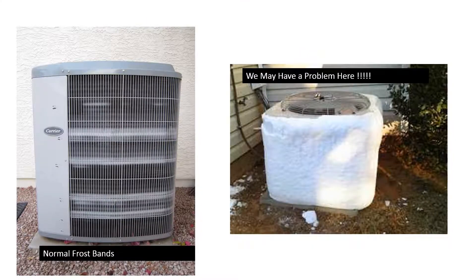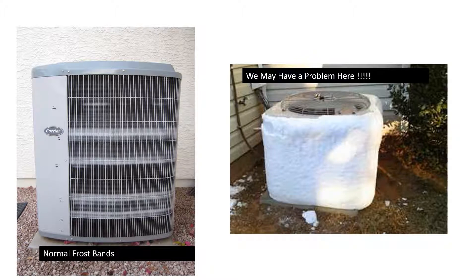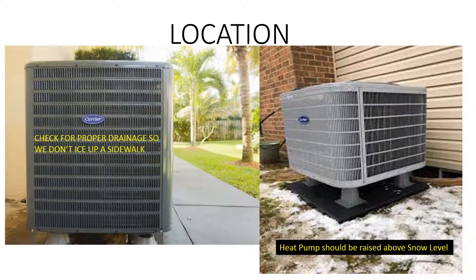The defrost cycle is a normal operation of any heat pump. In the winter, when the coil temperature reaches the freezing level and there's moisture in the air, frost bands will appear on the outdoor coil. The picture on the left shows the normal frost bands you will see on an operating heat pump during winter. On the right, if your heat pump looks like this, we may have a problem. In this video we're going to examine some issues with the defrost cycle.